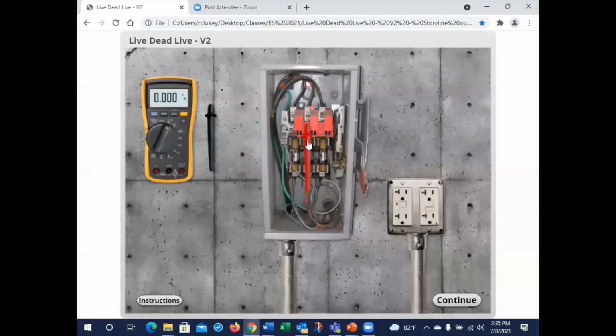Next, I'm going to go phase to phase. So I'm going to go from phase A to phase B. I can see I have no voltage. So somewhere upstream of this, because normally we know that I'm going to have to, if I'm going to do something inside this disconnect, which my task today is going to be verify all of these connections are properly torqued. And so that means I have to have the line side de-energized also. So I had to go upstream to shut the circuit breaker off, lock and tag it out. I did all that where these conductors originate from. And you can see, pretty good job because we are at 0. So A to B is 0. Then we come A to C.